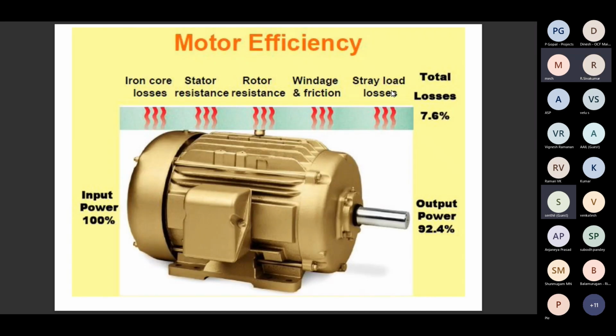See, normally in any industry, the motor load is very, very high, irrespective of production. The motor is a very major element in all industrial activities. Basically, motor efficiency depends on these losses. One is core losses, normally called iron losses, then the stator winding loss, called stator resistance loss, the rotor loss, the windage and friction loss, and the stray load losses. Windage, friction and stray load losses are less than 1.5% only, but the remaining iron core and stator rotor losses are very high.